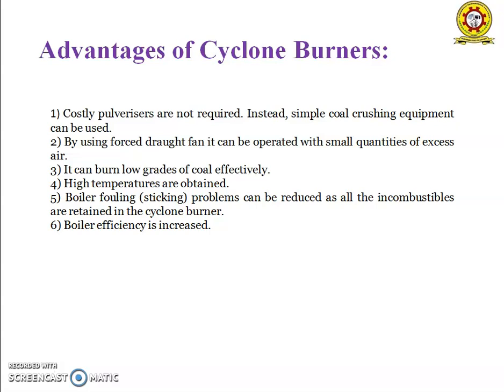It can burn low-grade coal effectively. High temperatures are obtained. Boiler fouling problems can be reduced, as all incombustibles are retained in the cyclone burner. Boiler efficiency also increases.